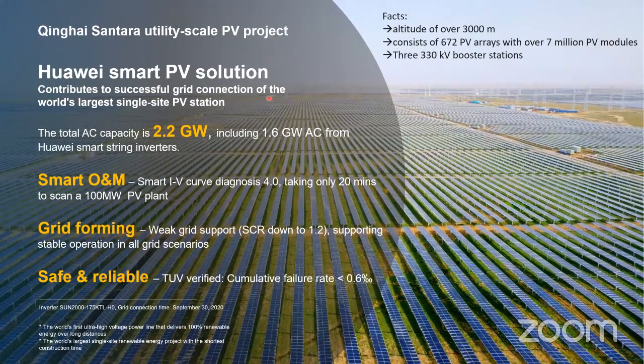The major portion of this power station is run through string inverters, and these are Huawei string inverters. All of these PV panels, which are the main investment, can be monitored and diagnosed with very fast diagnosing techniques. This power plant can also support weak grid scenarios, with short circuit ratios down to 1.2, and is already proven stable in all grid conditions at this moment, and is well certified with TÜV verification.